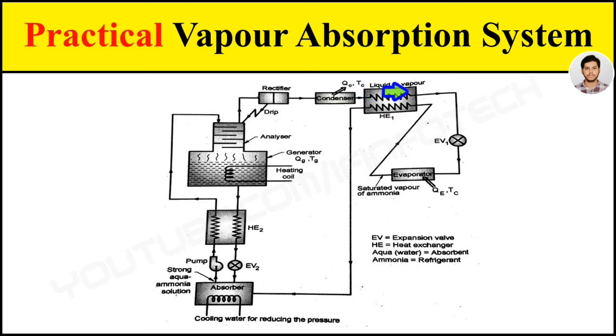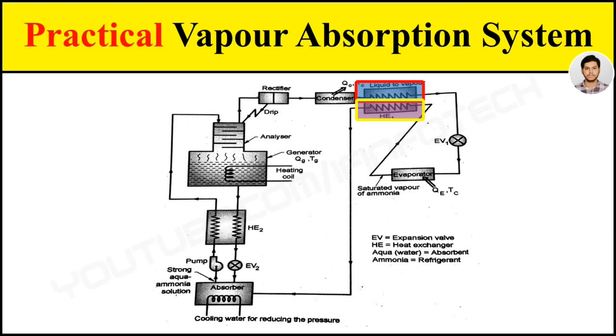This liquid ammonia is sent to the expansion valve through the first heat exchanger. The liquid refrigerant ammonia is sub-cooled by using low temperature ammonia vapor. This sub-cooled refrigerant is then passed through the expansion valve to the evaporator.